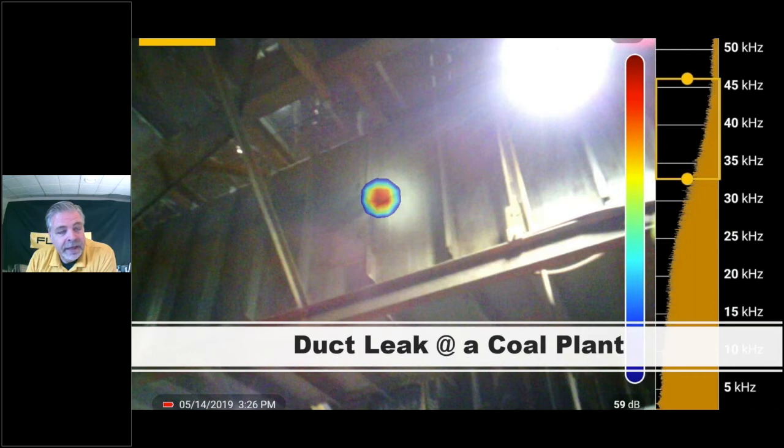they had a vacuum leak system. The only way they knew there was a leak was the vacuum gauge would drop off in terms of what it saw for vacuum. The other part of the problem was it directly created issues with their productivity and product quality. By putting the ii900 in service, they were able to find 3 leaks in literally 2 minutes, where before it was taking them somewhere in the order of an hour to find these leaks in all the piping systems they had. So it was literally a game changer for them.